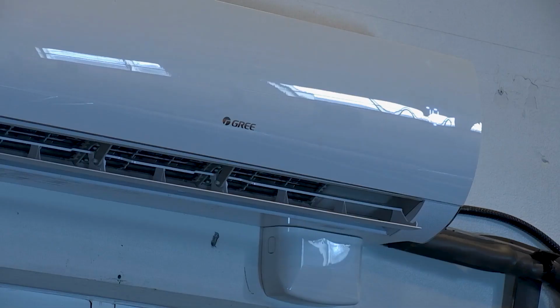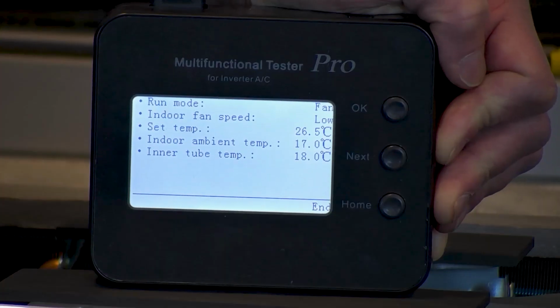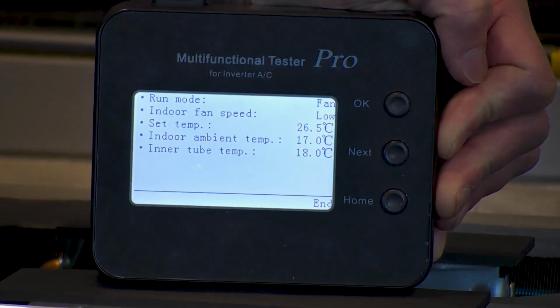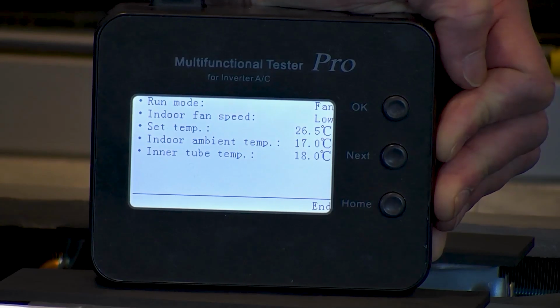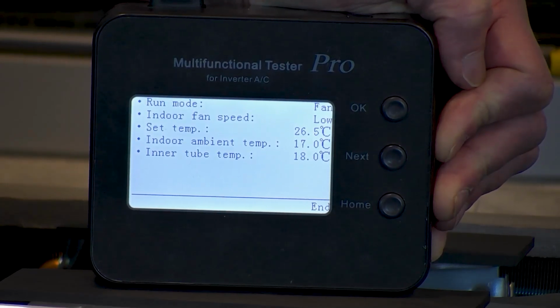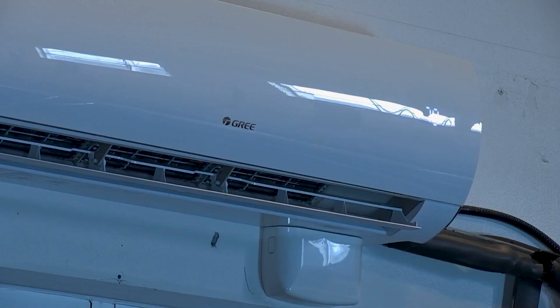There it goes. As you see, the indoor fan speed changed to low, and the run mode is also saying fan. So I'm not even hooked up to an outdoor unit. This tool is acting as our outdoor unit, and I was able to take the remote and put it in fan mode, turn the fan on. So at that point, I've just proven that the indoor and the outdoor units are 100% functional.